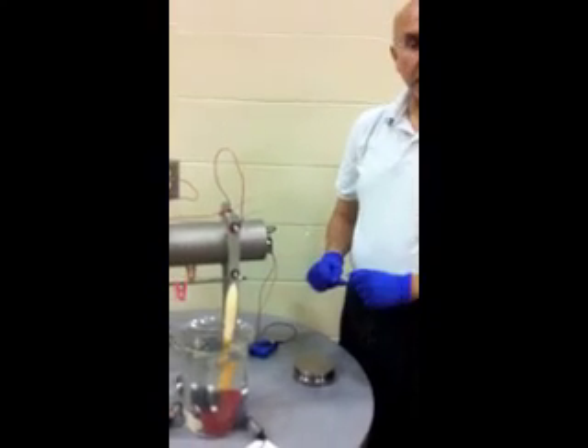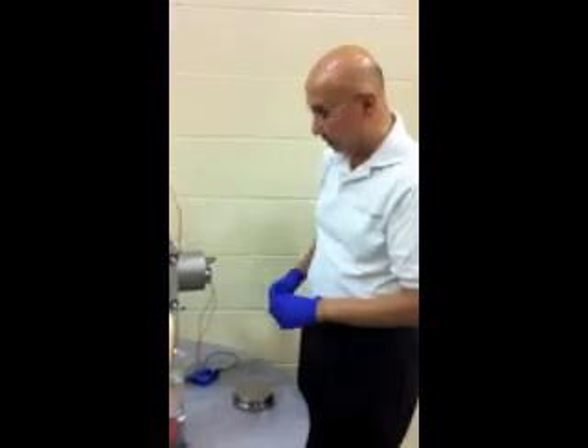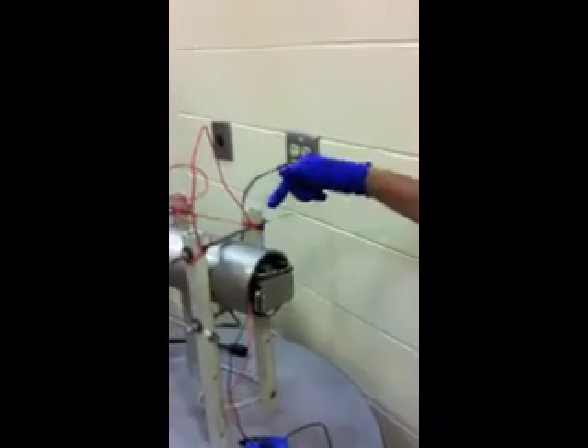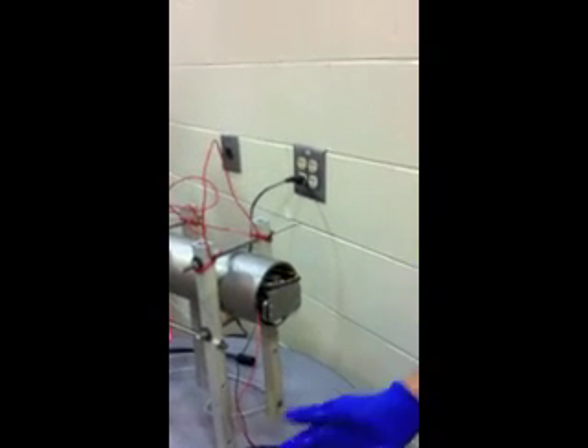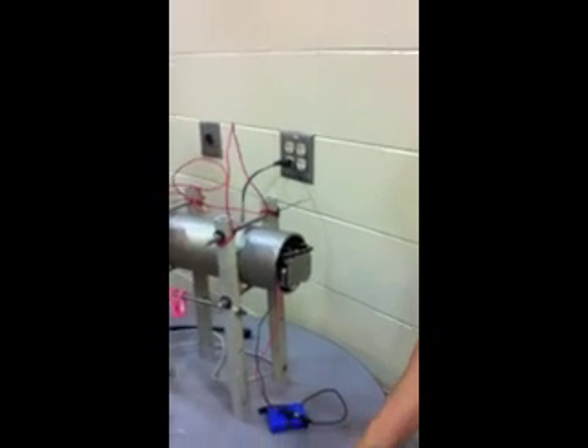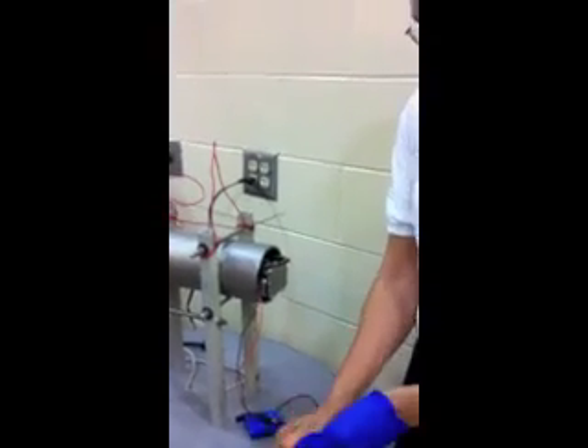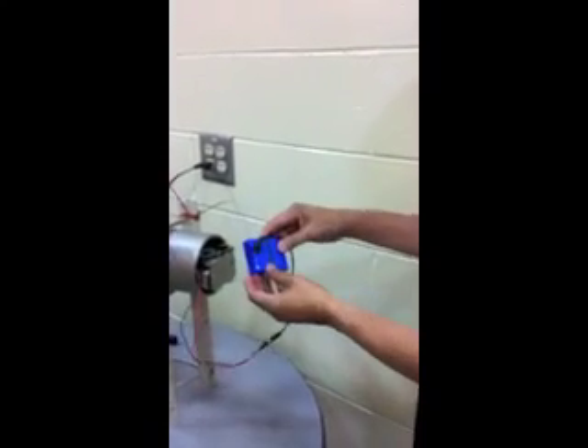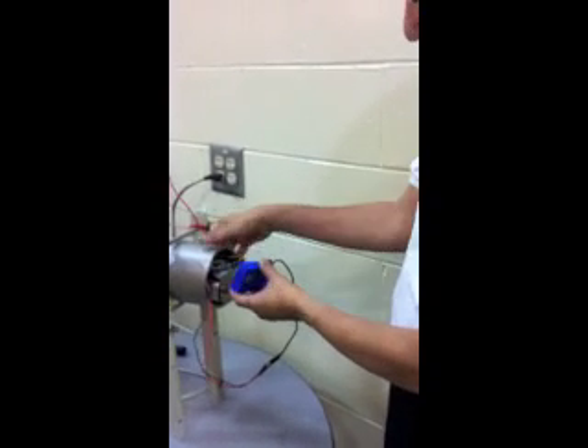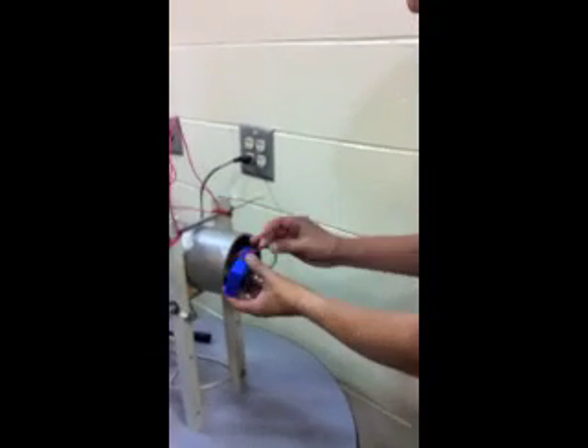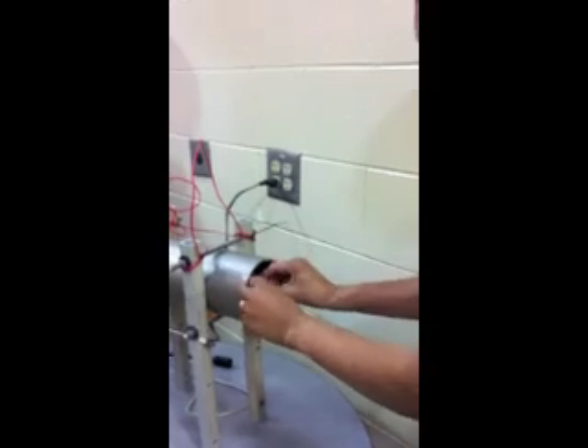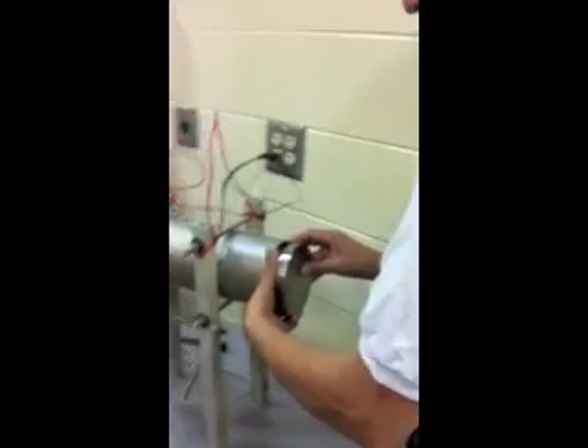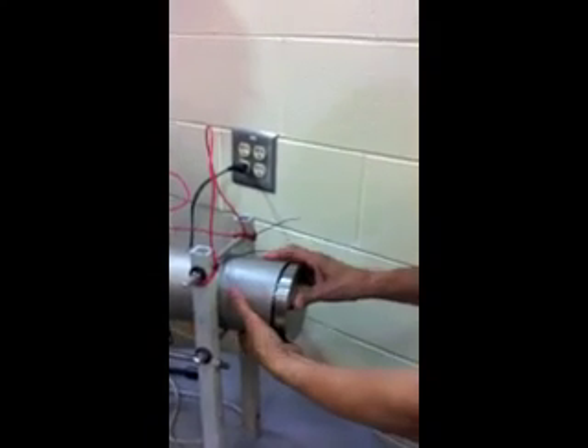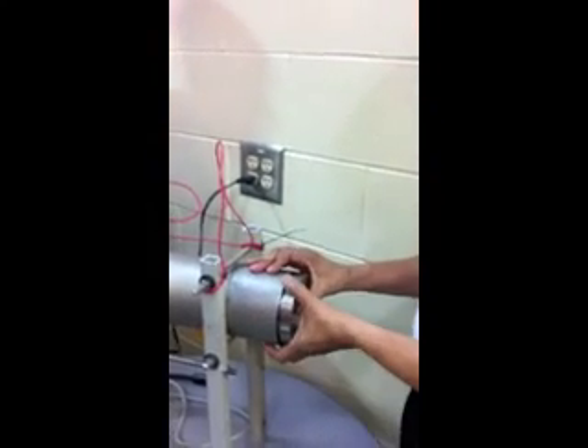Now, these sensors are going to be deployed, and we'll have a separate deployment video where you can view this. But this is the electronics end of the device. We have a housing here, which is cylindrical and is intended to withstand pressures in the deep ocean. And we have here several components. Our instrumentation and power supplies will be housed within there. And essentially this end consists of the data logger, which is within there, and a battery. And so the battery supply and the data logger all are inserted within this chamber, and we will provide all the detailed instructions. But essentially the end piece is then used to close the entire device, and all it takes is a little bit of pressure, and we will illustrate that a little bit later.